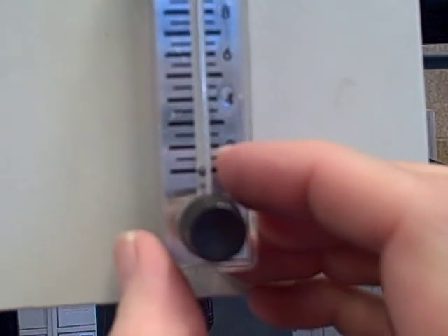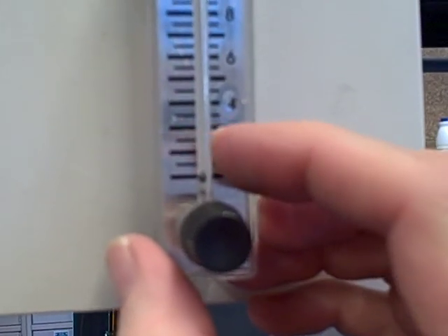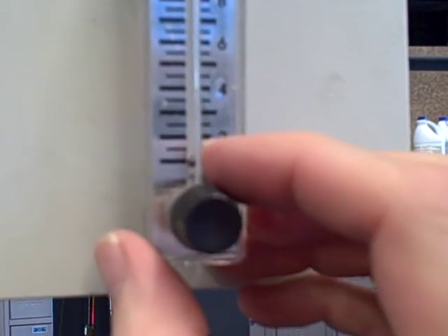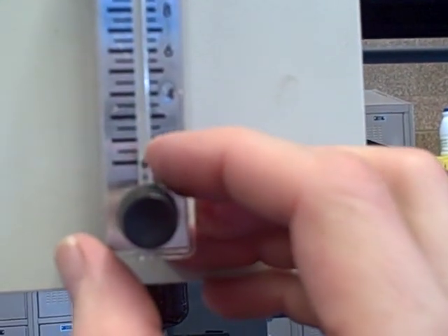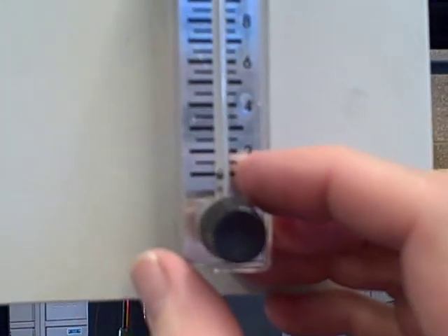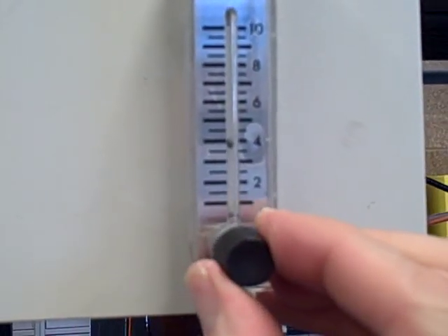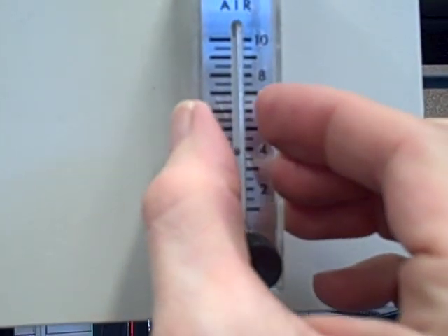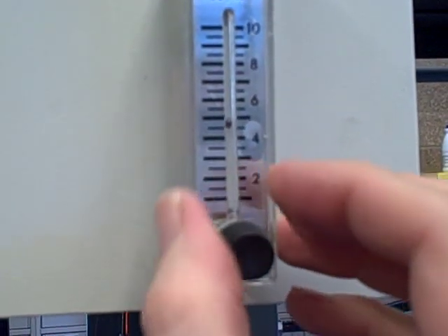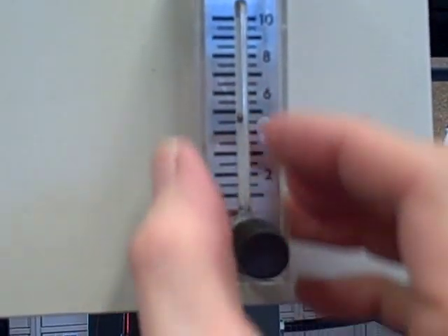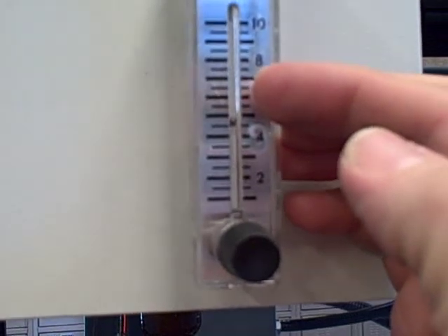that tube has a cone shape, starts small at the bottom and grows wider at the top. There's a small plummet inside that tube that's lifted up by the flow of fluid through it. Right now that plummet in this example is a small BB-sized ball of metal. And as I open up this valve, you can see that rises up. Because the tube grows wider as it goes to the top, more fluid leaks by, and it takes a greater flow rate to lift that plummet to a higher level.